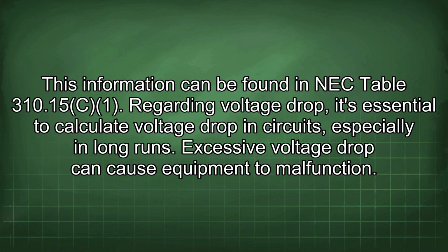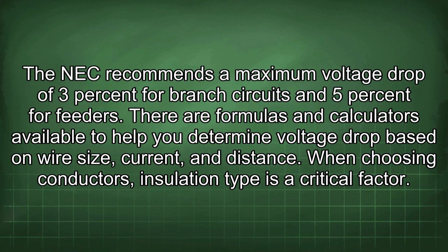Regarding voltage drop, it's essential to calculate voltage drop in circuits, especially in long runs. Excessive voltage drop can cause equipment to malfunction. The NEC recommends a maximum voltage drop of 3% for branch circuits and 5% for feeders. There are formulas and calculators available to help you determine voltage drop based on wire size, current, and distance.